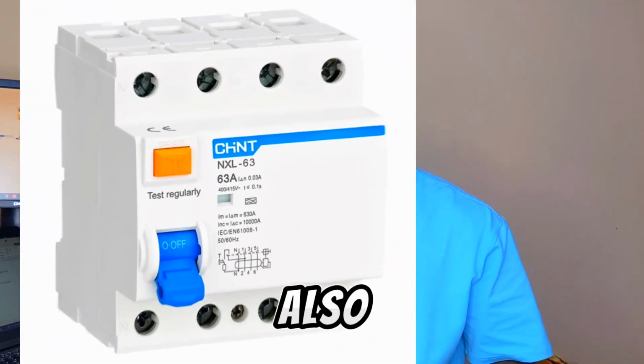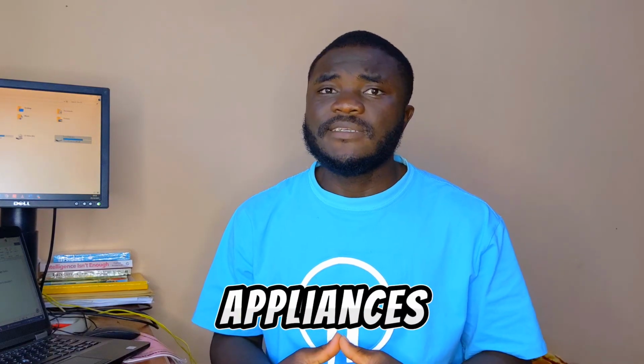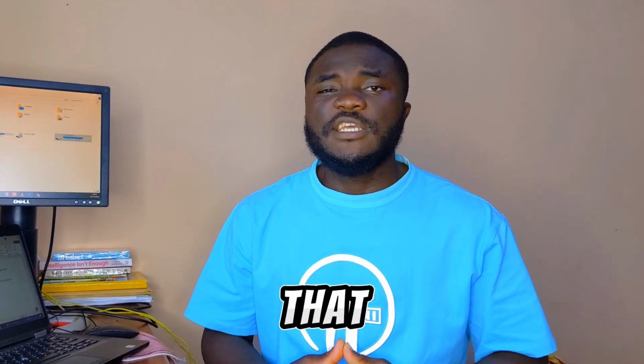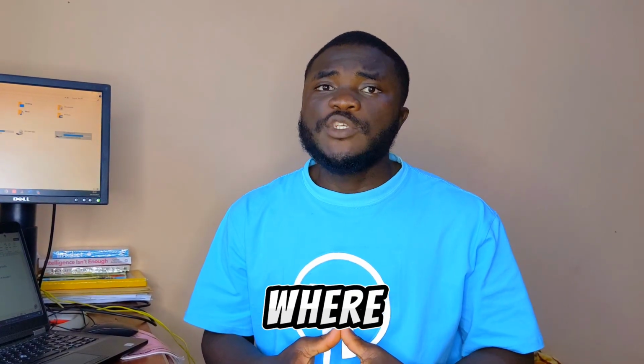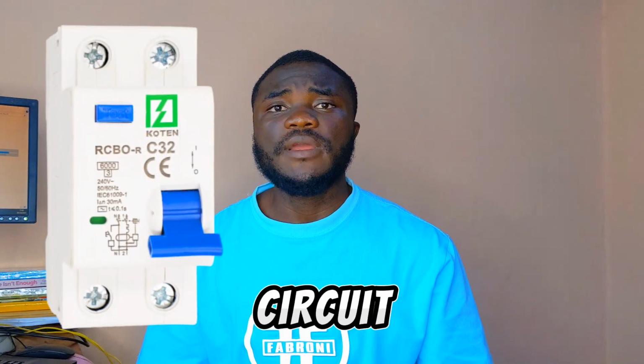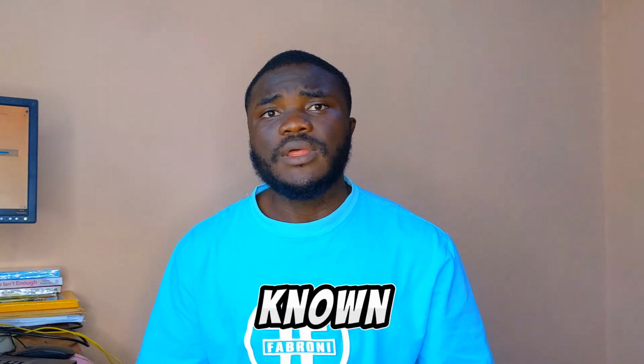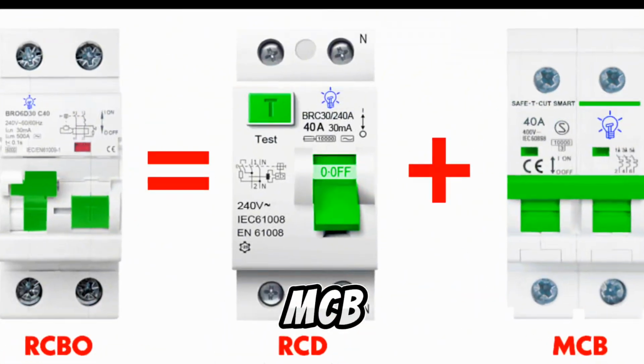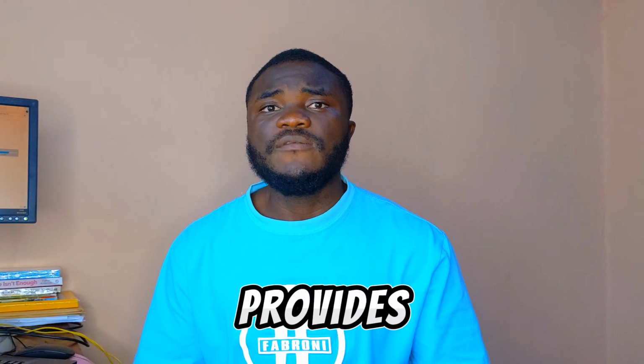And number 3, we have the residual current circuit breaker, also known as an RCCB. An RCCB protects people and not appliances. An RCCB protects against electric shock and earth leakage currents. Thus, it trips when electricity is flowing where it shouldn't, like at the back of your fridge. And number 4, we have the residual current circuit breaker with overcurrent protection, also known as an RCBO. An RCBO is basically a combination of an MCB and an RCCB. It provides protection against shock, overload, and short circuits all in a single unit.